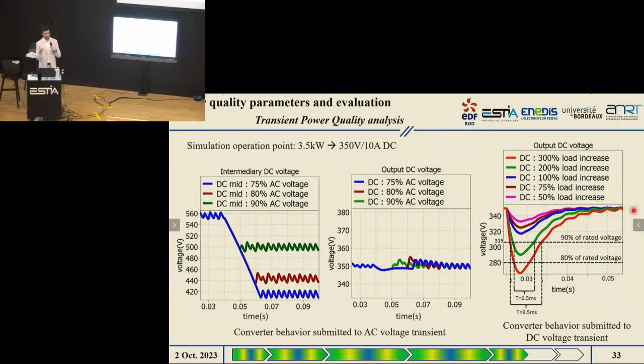And the same type of test was executed using load increase in order to create a voltage dip in DC. And once again, we can see that even for a 300% load increase, that you can see here in orange, our control is capable of bringing the voltage back into the rated voltage levels in acceptable time periods that were compared to the ones that we can find in the ITIC curve, for example.